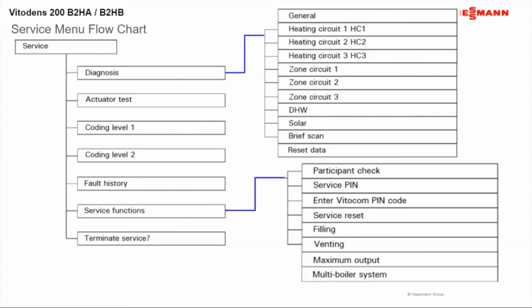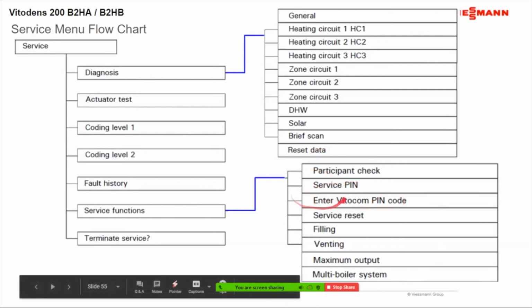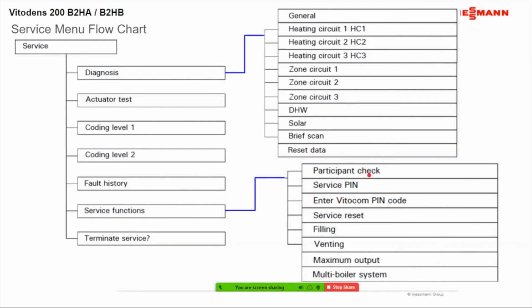Service functions. As you can see, the sub menu to the right hand side, as soon as you press that one, comes up. It says participant check, service pin, service reset, filling and venting. This stuff will disappear if you're doing multiple boilers. Participant check is for when you're tying into other boilers and you want to see if you're communicating to each other. I like to talk about the filling and venting mode, because a lot of guys don't know that's here. That filling mode is for when you're first initially filling the boiler with water. It exercises the pump to help you push the water through the coil of the boiler. So the pump comes on for a longer period of time to help push that air through the coil of the boiler itself. The venting mode is once you've done the fill and you've got it pretty much filled.